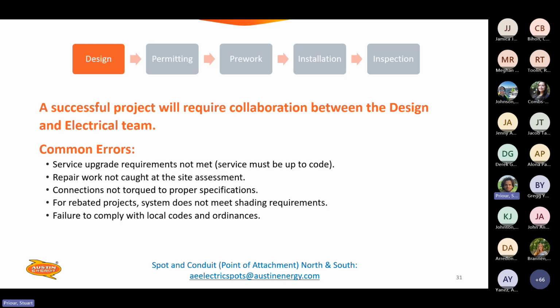Another problem that we see often is that connections are not torqued to proper specifications. This is critical, especially in meter cans and for supply side taps. We've seen some instances of burned up taps if they're not properly torqued. For rebated projects, you've got systems that do not meet shading requirements, and also failure to comply with local code and ordinances. If you've got any questions, you can also contact Spot and Conduit at that email address below, aeelectricspots@austinenergy.com.